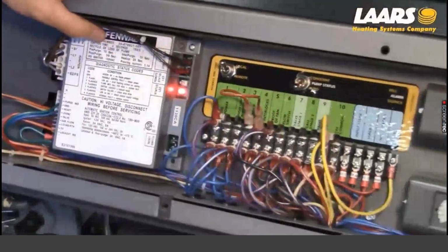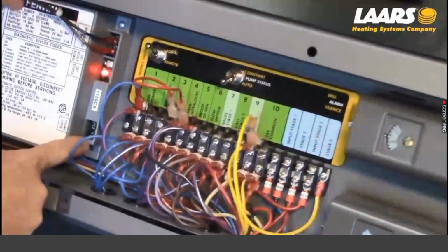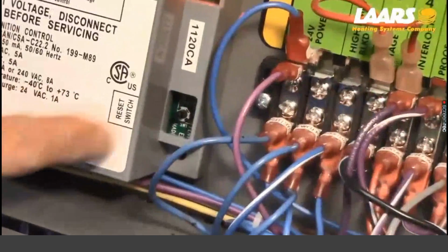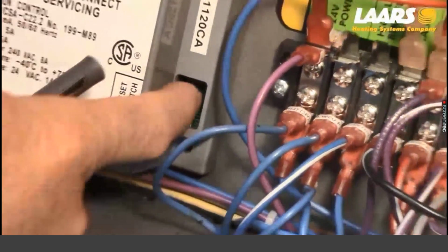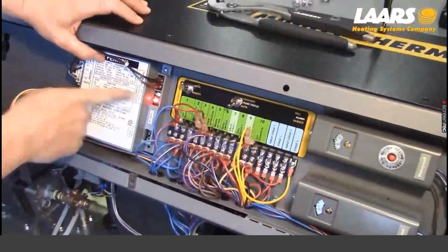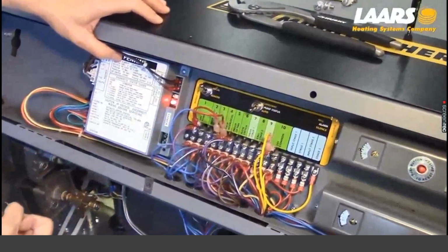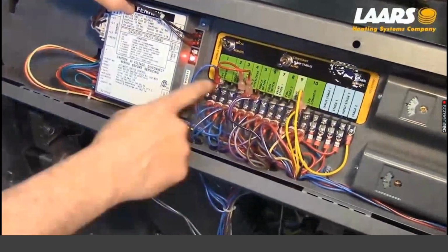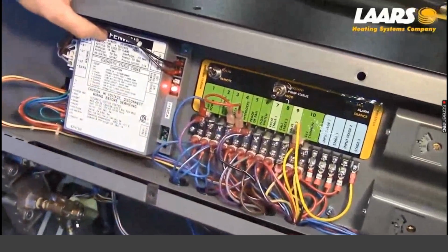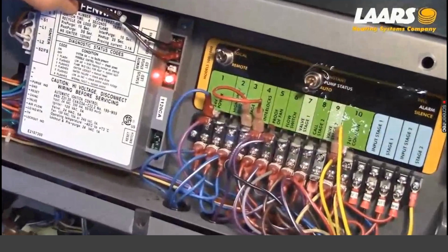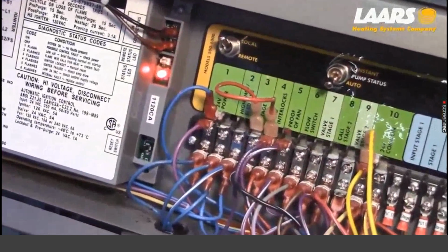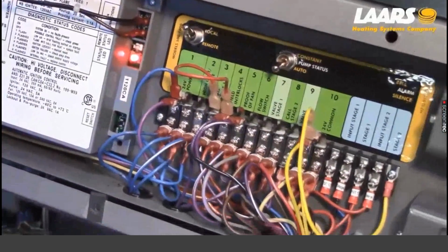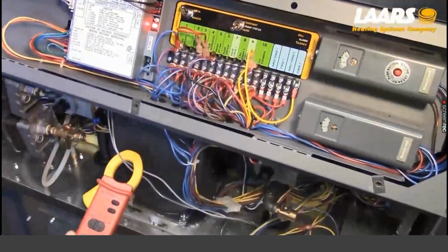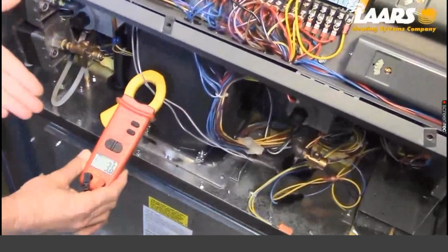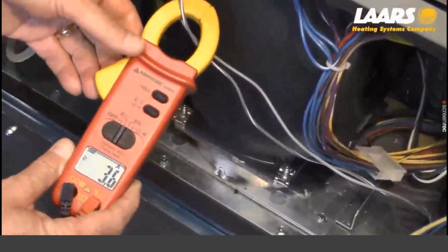1 single flash would be low air. So there's a reset button right here, that little black reset button right there. That is reset for the ignition control. So I'm going to press the reset button, and now we have a steady on light. Once the fan comes on and proves the fan, and our flow switch and everything else in the safety chain is made, we'll see a single flash. And now with an amp probe, I can put my amp probe on either one of the wires, and we'll see that we're looking, again, 3.4 or greater for amperage, okay? If we don't, that means you have a bad igniter, and that's why we went into the ignition fault.